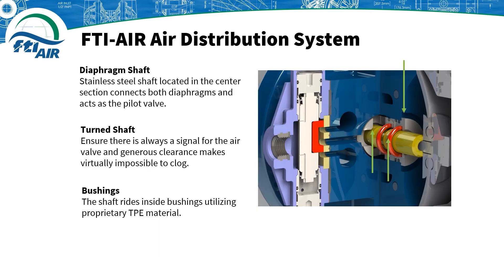A simple design equals reliable design. The diaphragm shaft in the center section serves two functions: it connects both diaphragms and acts as the pilot valve. The pilot valve is responsible for signaling the pump when it is time to shift from one direction to the other. Using a turned shaft in our design ensures it always gives a signal to the air valve and has generous clearances to prevent clogs.